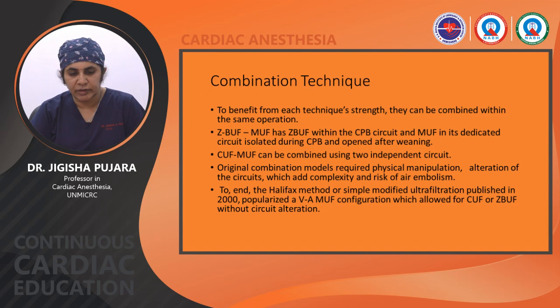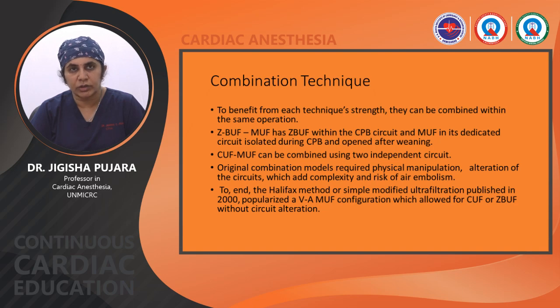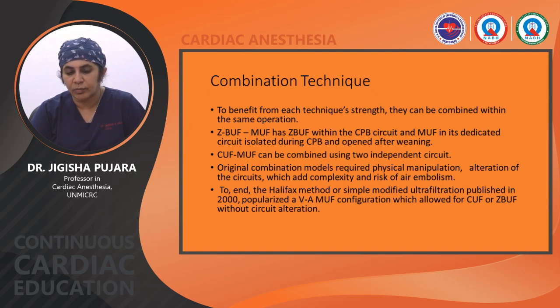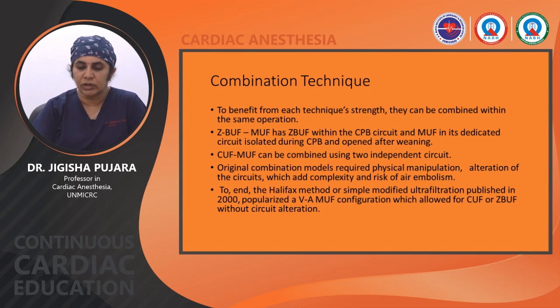Various combination techniques benefit from each technique's strengths and can be combined in the same operation. Z-BUF combined with MUF uses Z-BUF within the CPB circuit and MUF in a dedicated circuit isolated during CPB and opened after weaning. CUF and MUF can be combined using two independent circuits. The Halifax method — simple modified ultrafiltration — published in 2000 popularized a V-A MUF configuration allowing CUF or Z-BUF without circuit modification.